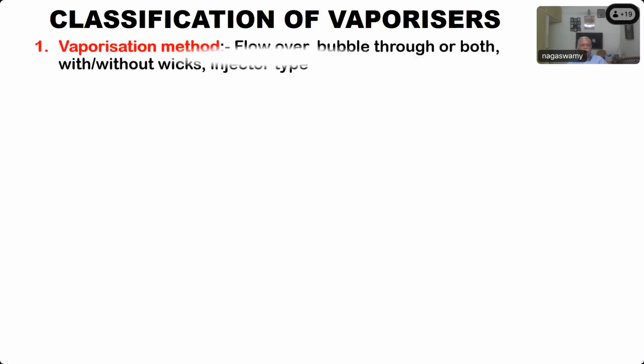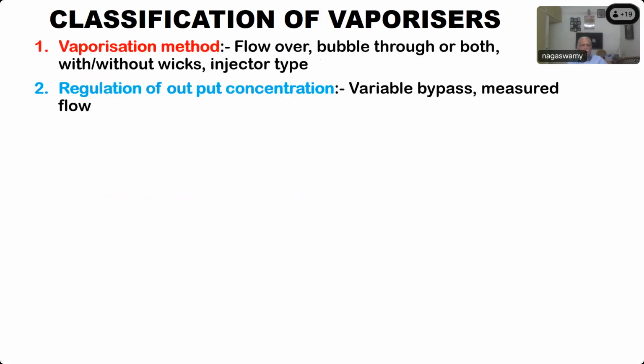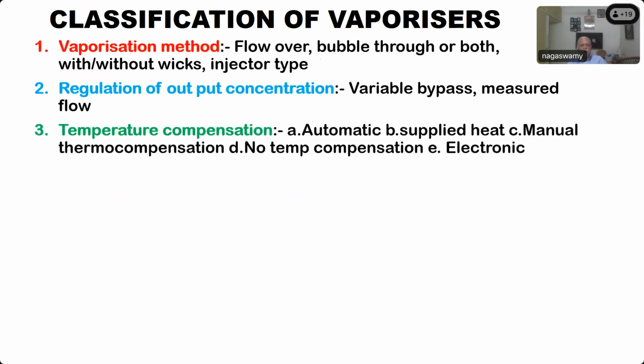So how do you classify the vaporizers? This is another question. They can be classified as flow over, bubble through, or both flow over and bubble through, with or without wicks, or injector type. Okay, these are all the various vaporization methods. And how is the regulation of output concentration? It is by variable bypass or measured flow. And temperature compensation can be automatic or supplied heat, or manual thermocompensation, no temperature compensation, or electronic. So 5 methods are there.